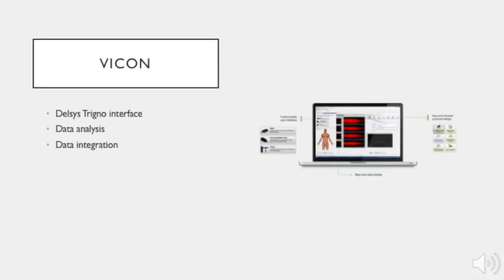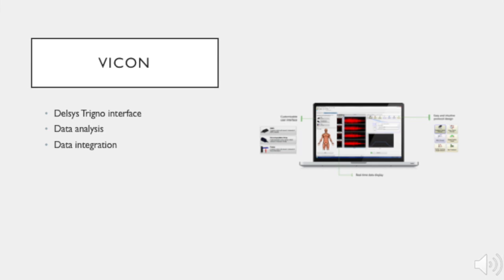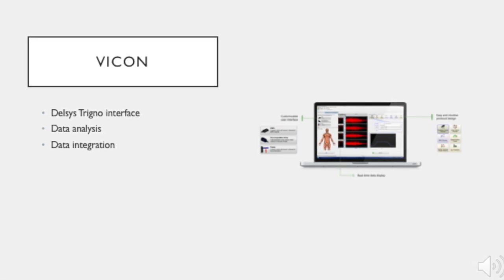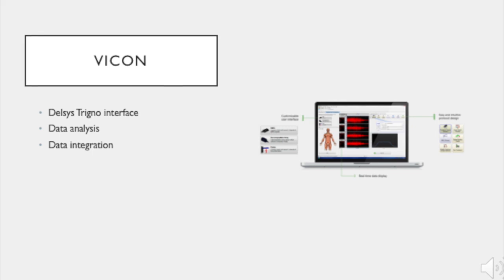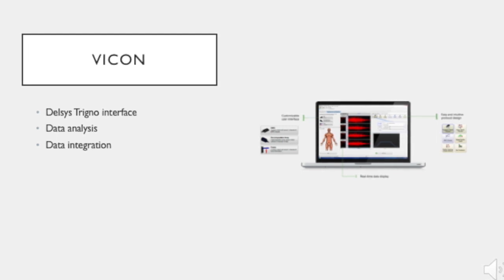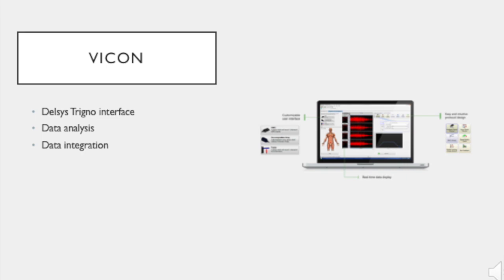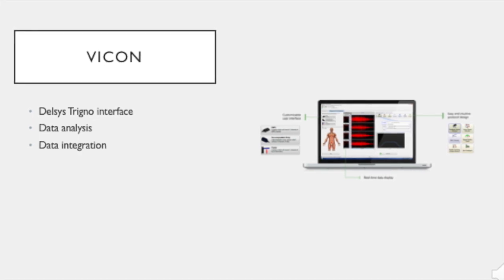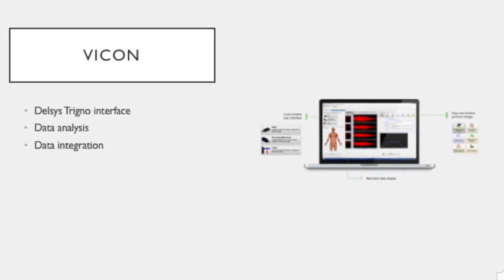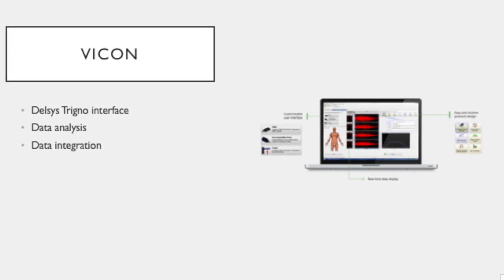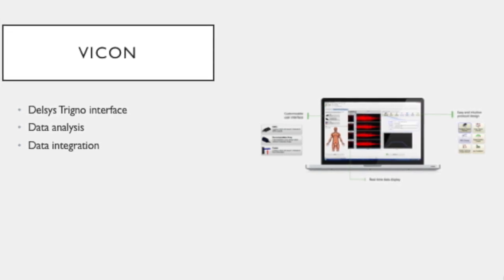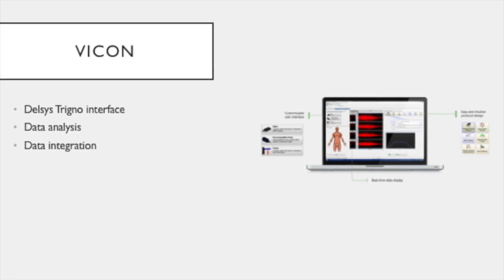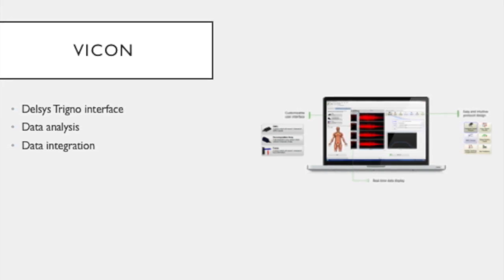DELSYS-Trigno allows you to use multiple third-party programs to interface with the EMG system. We will be using Vicon's motion capture system to interface with the wireless EMG. The Vicon system allows you to view the EMG and accelerometer data for the EMG sensors while facilitating the parallel analysis of data collected using Vicon's motion capture and force trace capabilities. The following video will show how to connect the DELSYS-Trigno and Vicon systems in order to collect EMG data through the Vicon system.